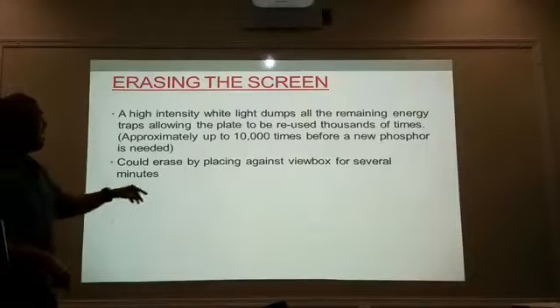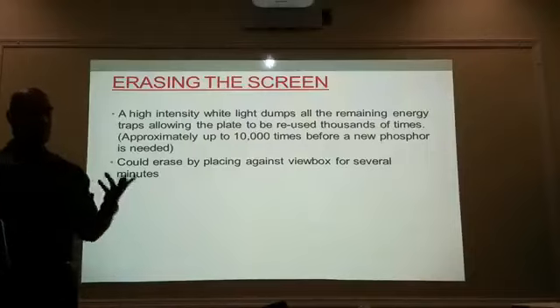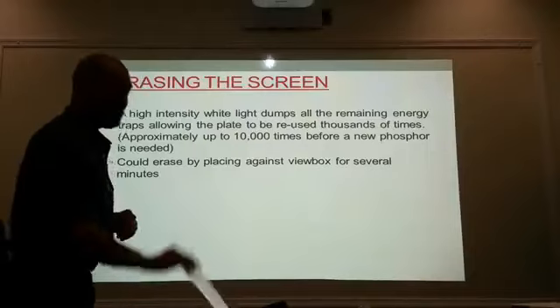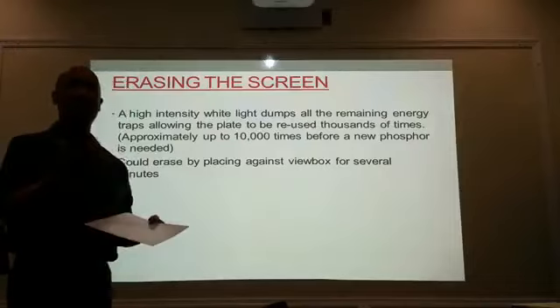We actually have a lab in which we take an x-ray, take our PSP out and leave it under white light, put it back into our cassette, and see if there are any remaining images on it.